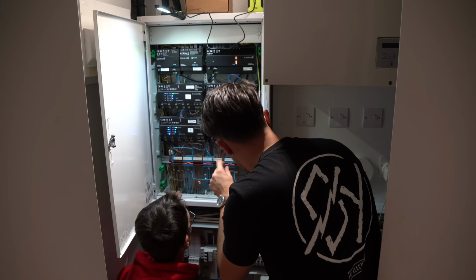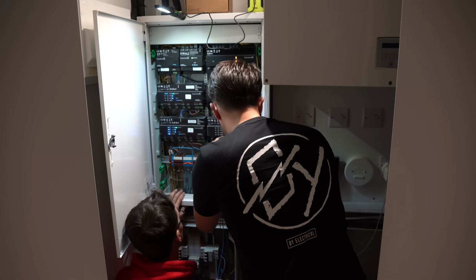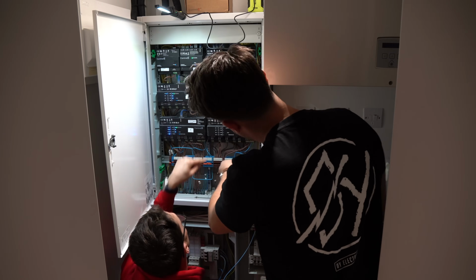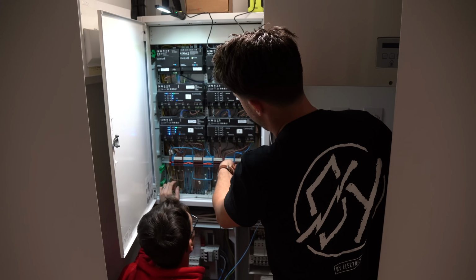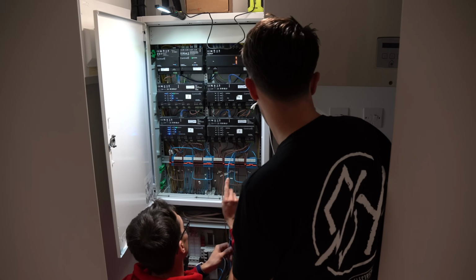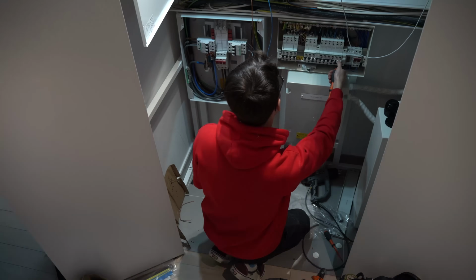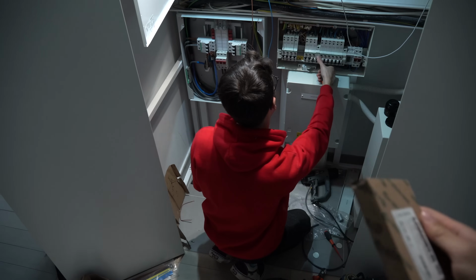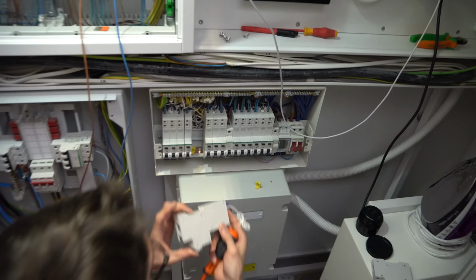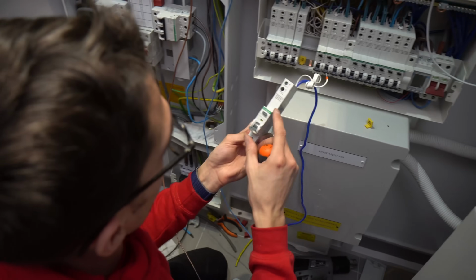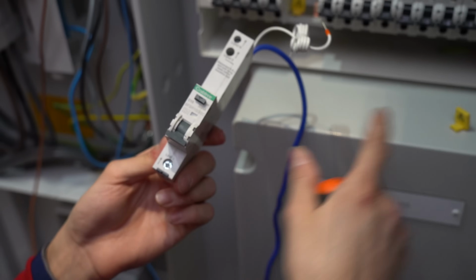So I've split this off best I can. We could just temporarily put it on and see if it trips. I think you're right. I can't see any neutrals going across. But I reckon there's going to be one that's in the wrong place. So we've got the, it's got very dark all of a sudden. What are you doing here, Ollie? So we've got a C10 Crabtree RCBO. So the next spare way, we're just going to put it over here.